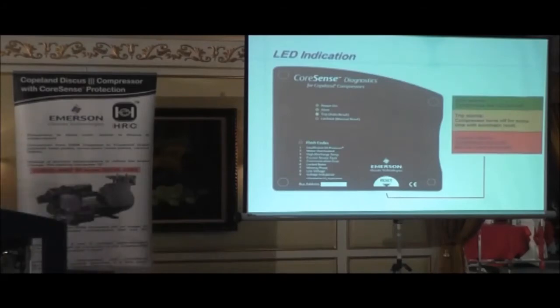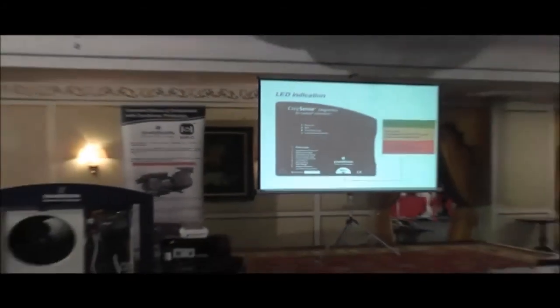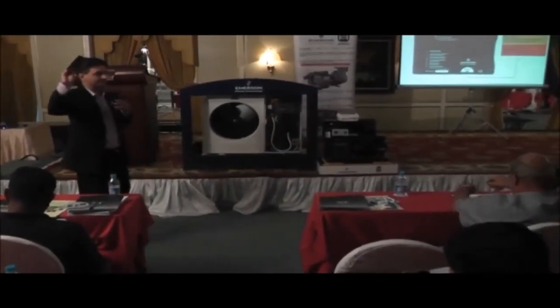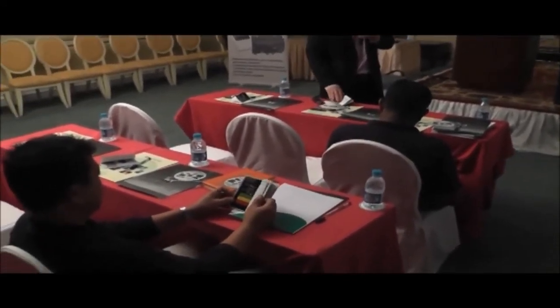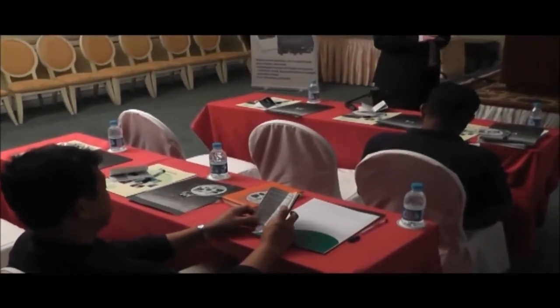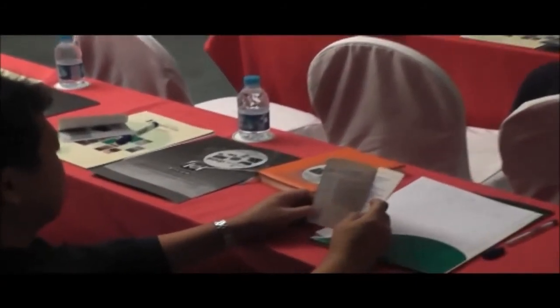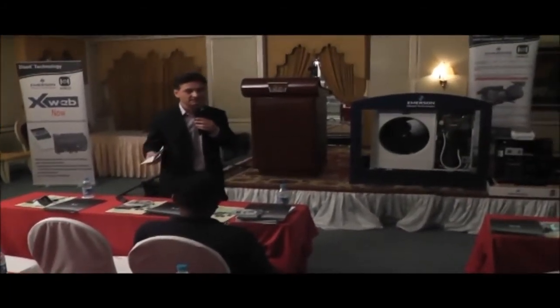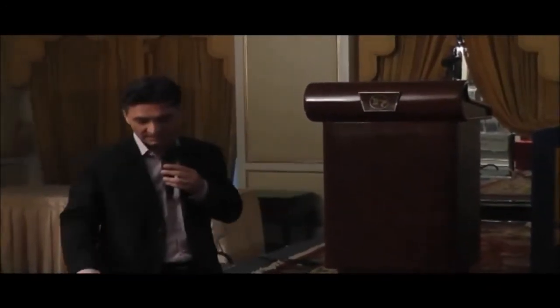On your table, you have a small little booklet. Just this booklet here. There should be one on every table. Basically what this booklet does is it gives you, depending on what the LED status is and the flash code, the alarm condition, what the possible reasons are, and tips for troubleshooting. What can I look for at the compressor or in the system to try and rectify the problem. Okay. So in this booklet, it starts with the green code, it then transitions to yellow, and then finally to red. And red means it's a manual lockout. So you need to repair the problem and then reset the module.